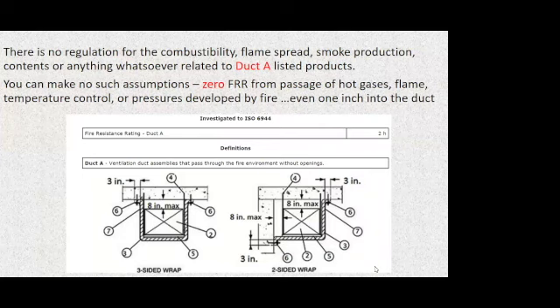That's my sanity check, and I don't understand how we step over that basic sanity check to get to duct A for these life safety applications that are so much harder than grease duct. So unfortunately, flip through the directory if you ever have time to kill. Open up the UL online directory, click on fire rated duct. I think it's 30 odd, slightly less than 40 designs that you'll find in there. And 9 out of 10 of them are going to look like this.